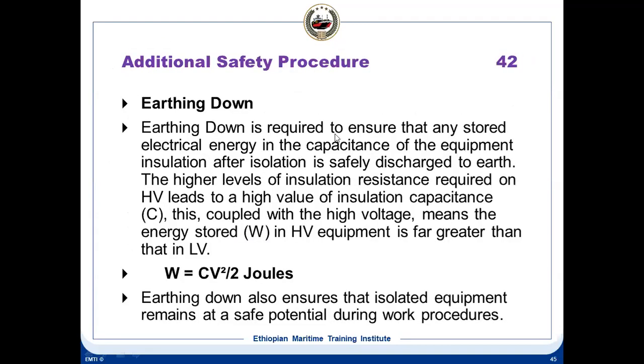Earthing down is required to ensure that any stored electrical energy in the capacitance of the equipment insulation after the isolation is safely discharged to earth. Earthing down means any residual charges which are there are to be grounded. So some special grounding cables have to be connected, or it has an inbuilt ground switch.